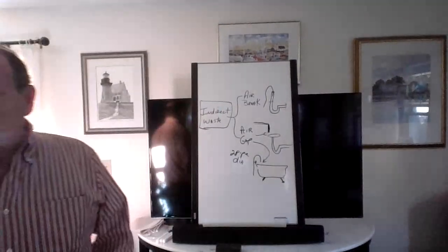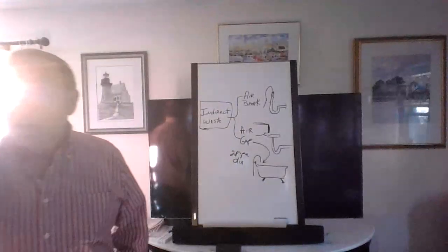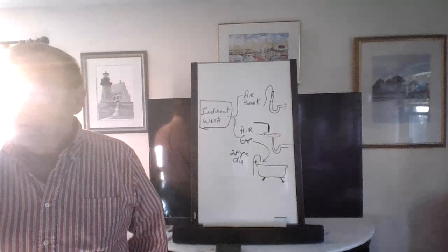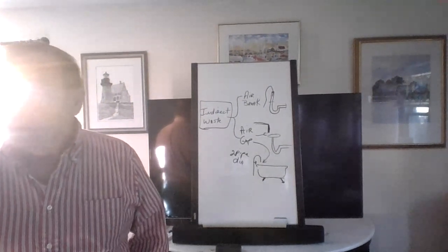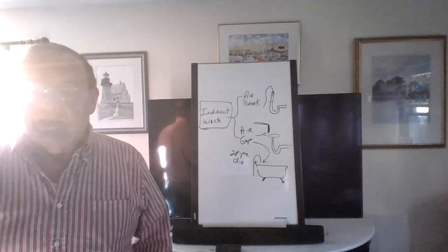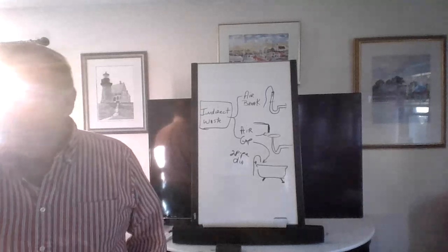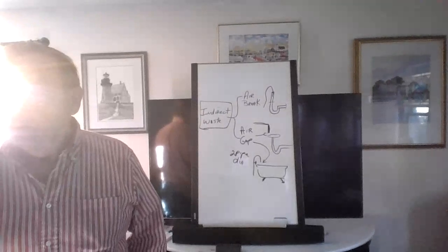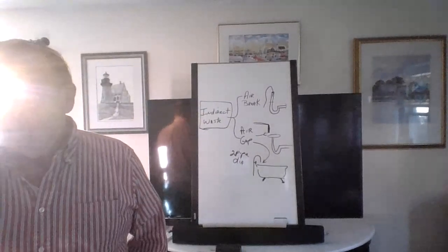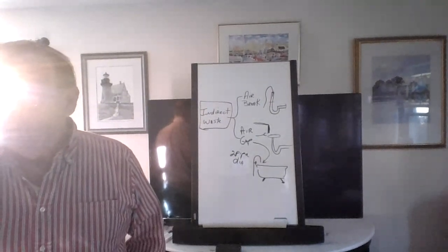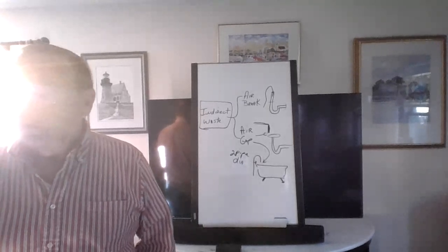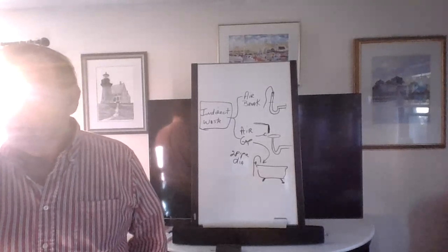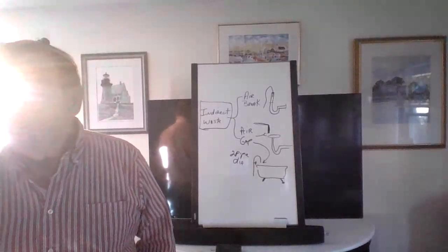Now, barometric loop. This is down almost about a third of the way down the page. This one is really something for your license. In theory, water cannot siphon if you got a loop 35 feet high, right? Water won't siphon that high. You can only siphon maybe, I think, 20 some feet practically, but 35 feet, nothing's going to siphon. So a barometric loop, 35 feet high, would fill in for a backflow preventer. Okay, they mentioned back siphonage. Same thing. All right, water going the wrong way.